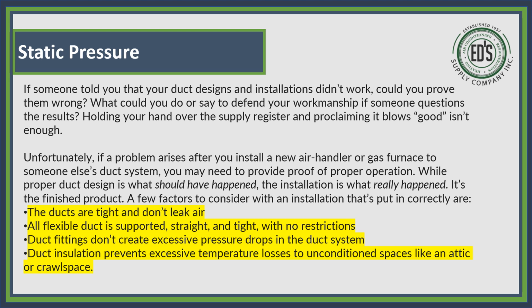Unfortunately, if a problem arises after you install a new air handler or gas furnace to someone else's duct system, you may need to provide proof of proper operation, while proper duct design is what should have happened. The installation is what really happened. It's a finished product.